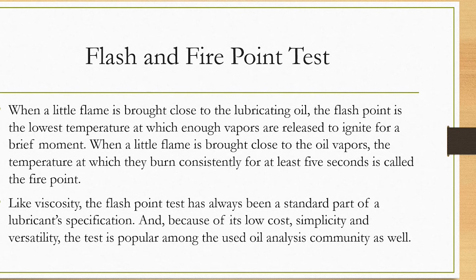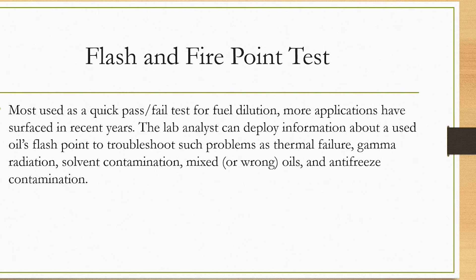The flash and fire point test is trial-and-error based — it is not calculated mathematically but determined by the apparatus itself. It is most used as a quick pass or fail test for fuel dilution, and more applications have surfaced in recent years.